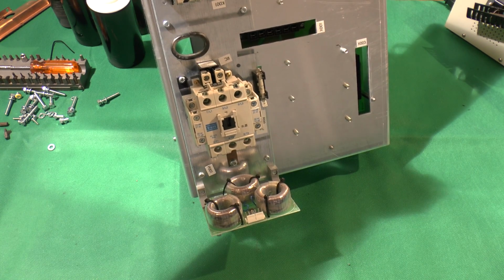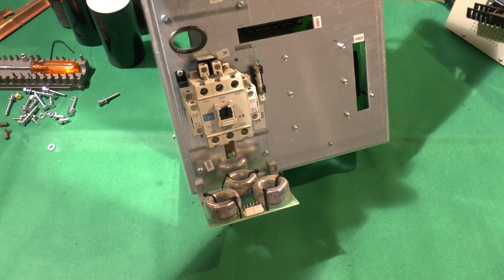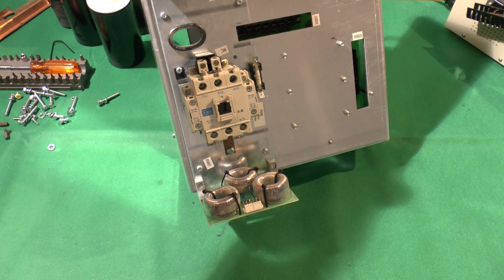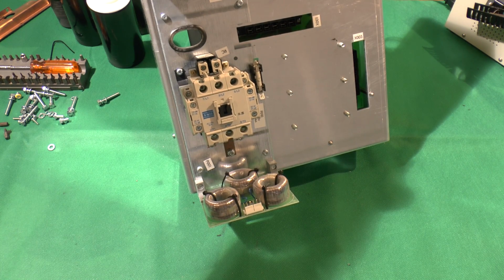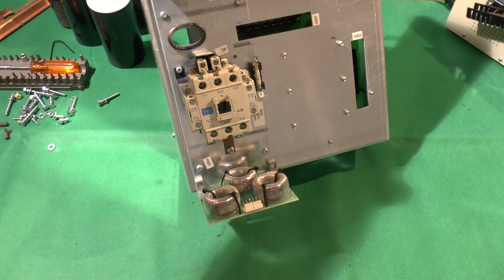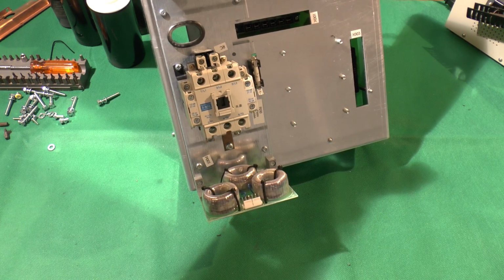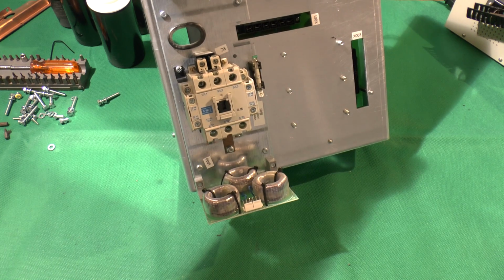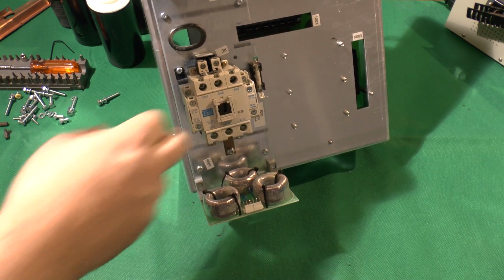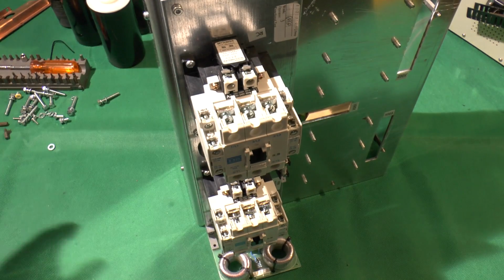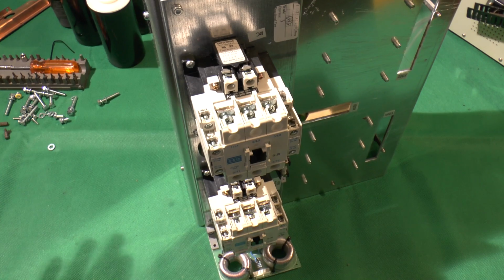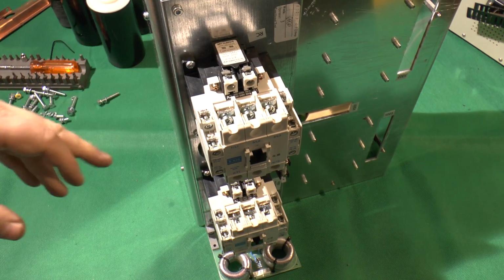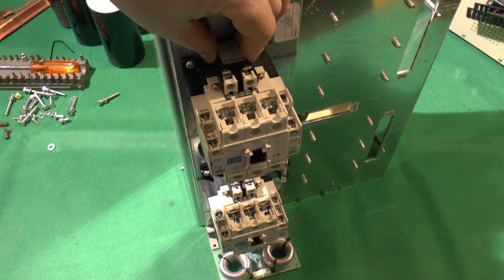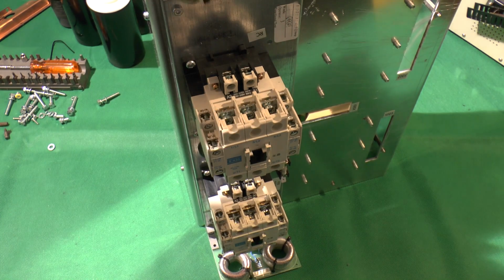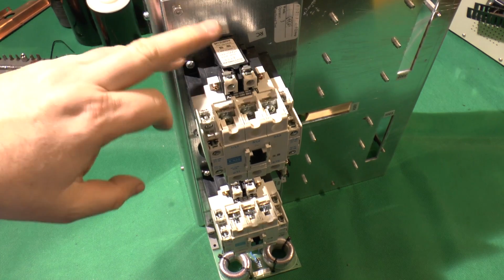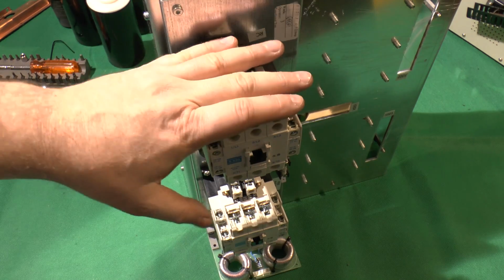I think, looking at this and some stuff online, one is a backfeed protector, so if all of a sudden the UPS is providing power, all it's doing is providing power out, it can cut the power and make sure it's not back feeding. And the other one will be a maintenance bypass, which will completely pass all the input straight through to the output, so the UPS can be put into maintenance. I think that's what these will be anyway. So that's on the one side.